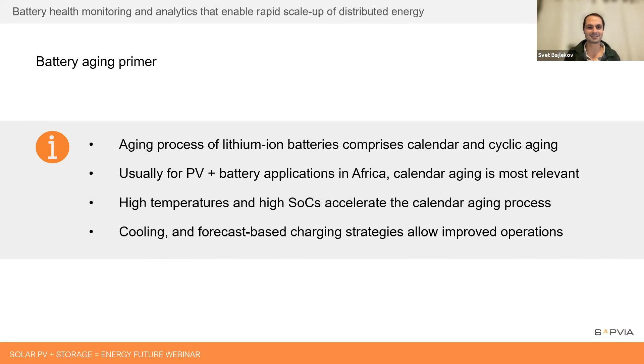So the main takeaways: firstly, we were successful in getting some really valuable insights from this data set, monitored over 11 months. Despite the limited data points and limited resolution, we were able to translate that, with Akira's help, into some pretty granular and reliable state of health estimations and aging estimations. We found that aging varies significantly based on operating conditions, and doing the analysis and seeing the data was really insightful. One of the most eye-popping things was that out of 14 systems, one was basically on the brink of failure just 2 years after installation. I'll say a few more words about that.